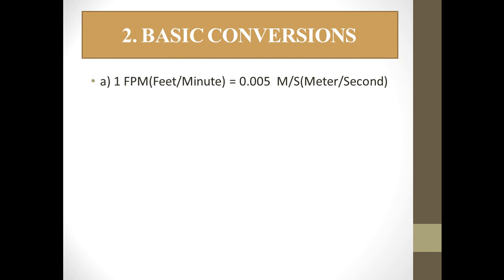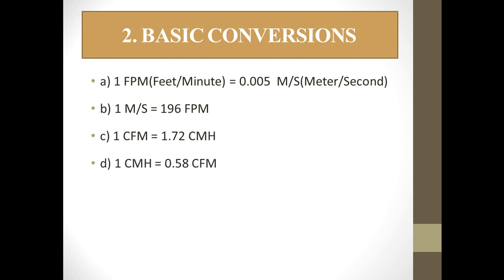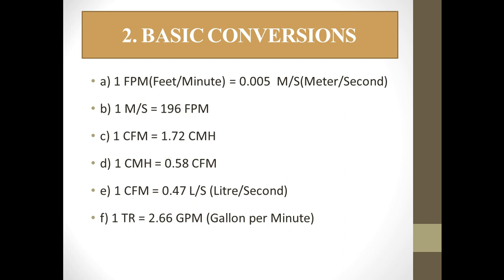Continuing with basic conversions for velocity and flow rates: (a) 1 FPM (feet per minute) = 0.005 meters per second; (b) 1 meter per second = 196 feet per minute; (c) 1 CFM = 1.72 CMH (cubic meters per hour); (d) 1 cubic meter per hour = 0.58 CFM; (e) 1 CFM = 0.47 liters per second.